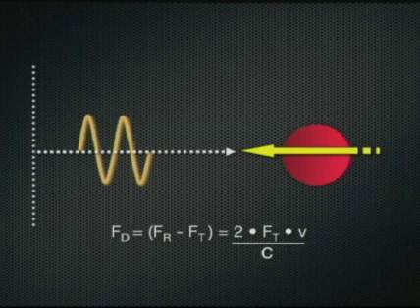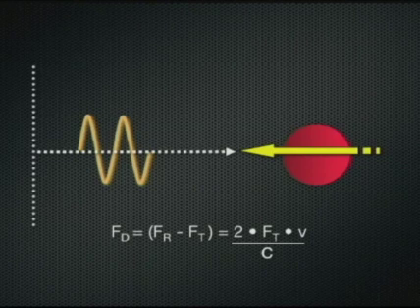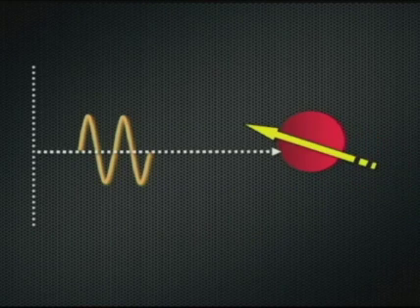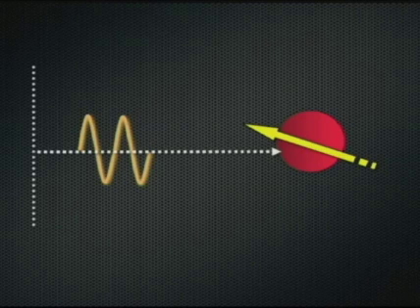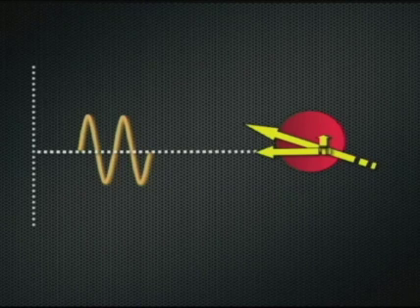In clinical situations, however, this relationship of the transducer to the moving object usually doesn't exist, and the blood is usually moving in a vessel at some angle to the direction of insonation. In this case, a component of motion is directed towards the transducer, the large arrow, and a smaller component is directed at 90 degrees to the direction of insonation.